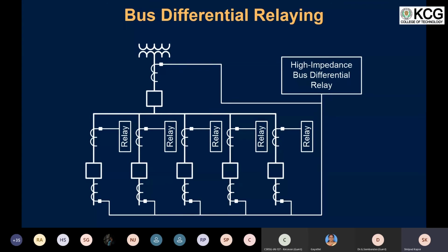There is another method which uses the high impedance bus bar scheme. In the high impedance bus bar scheme, you would find that a dedicated relay is installed just to do the differential protection for the particular bus bar. Any differential scheme works on Kirchhoff's current law, wherein if the sum of the incoming current is not equal to the sum of the outgoing current, the difference is provided as a differential current.